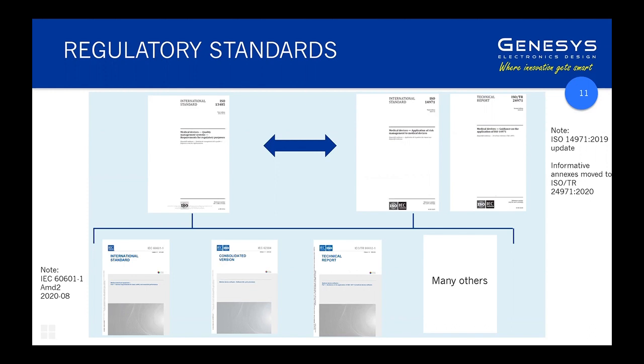So 60601-1 for electrical medical device safety is very heavily focused on risk management. It's mentioned dozens of times through the document. And also 62304 explicitly calls out 14971. And there's a technical report, TR 80002-1, which gives guidance on how to apply 14971 in the software compliance environment.